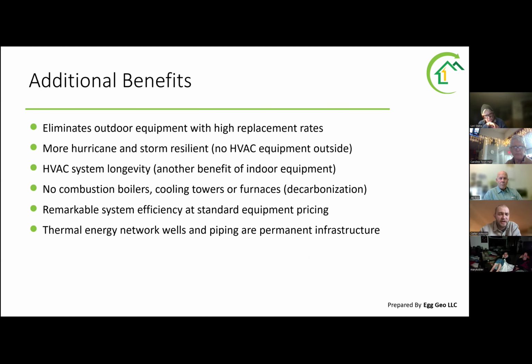There are lots of additional benefits talked about in the report that didn't quite make it with a whole slide and a figure here. A system of this type, regardless of the technology you choose, will eliminate outdoor equipment, which has high replacement rates. It's also much more storm resilient, taking all your outside equipment and essentially putting it inside. Your system longevity will increase. No more combustion boilers, no cooling towers or furnaces, which has a decarbonization component to it. Way higher system efficiency, the ability to share energy, and the efficiency of a hydronic system like this.